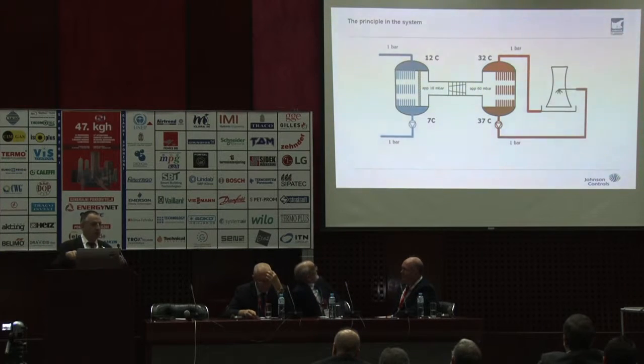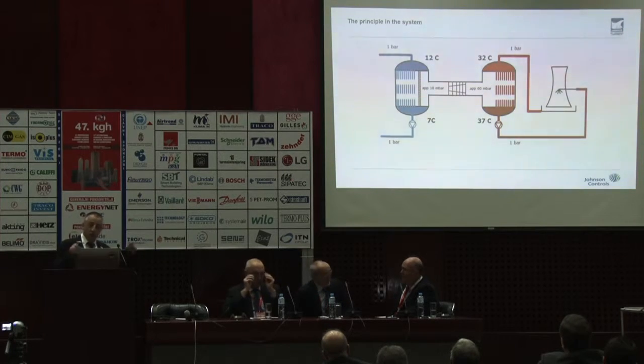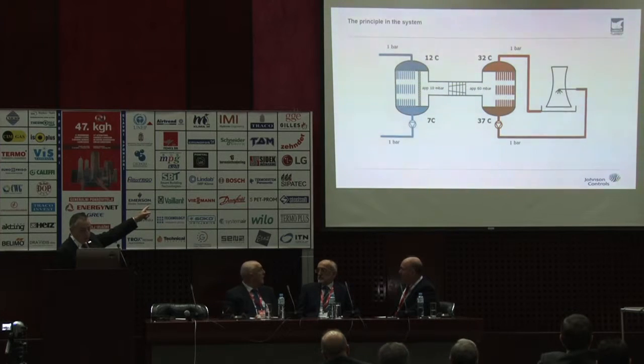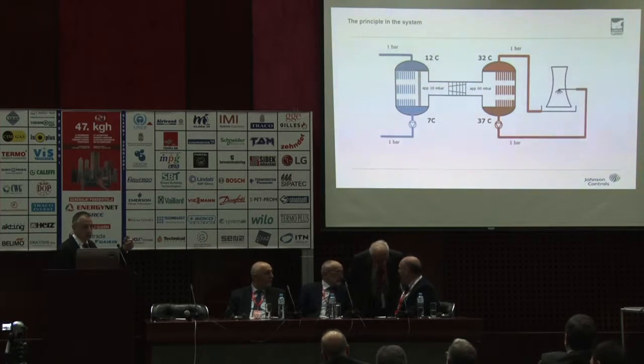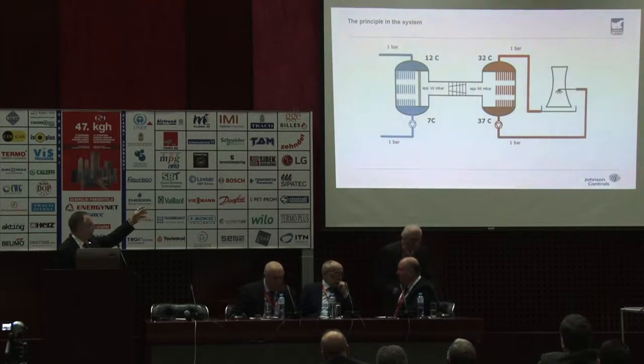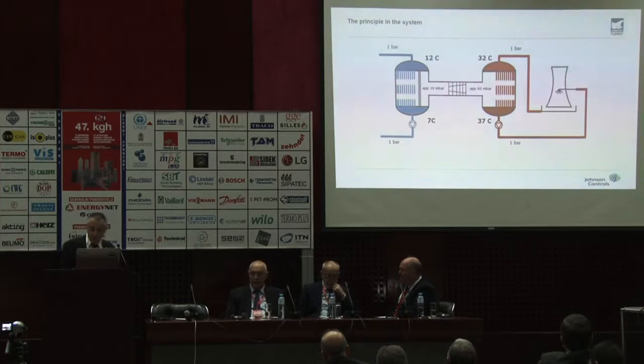And the open system here is the most efficient, but I have some numbers coming up in a moment. So you will throw out, but you can also close and make a dry cooler instead of the cooling tower, and then you have to recirculate the water back. But you will normally here accumulate all minerals in the water. You will accumulate that in the evaporator. So if we are putting in the water here, we will have to clean it out now and then. Means that you have to break the vacuum and clean it. It's a technical challenge, but not a big one.